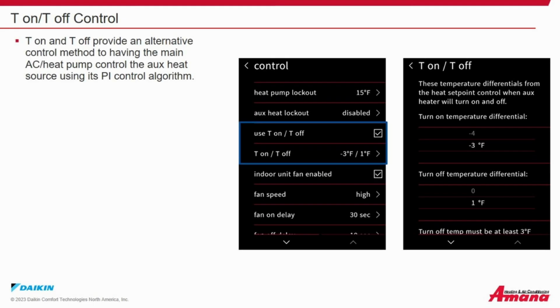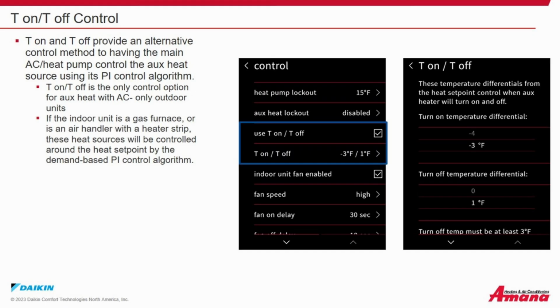T-on, T-off control. T-on and T-off provide an alternative control method to having the main AC or heat pump control the auxiliary heat source using its PI control algorithm. T-on and T-off is the only control option for auxiliary heat with cooling-only outdoor units. If the indoor unit is a gas furnace, or if it is an air handler with a heater strip, these heat sources will be controlled around the heat set point by the demand-based PI control algorithm. When T-on and T-off is selected, the auxiliary heat source will be controlled independently using these settings.